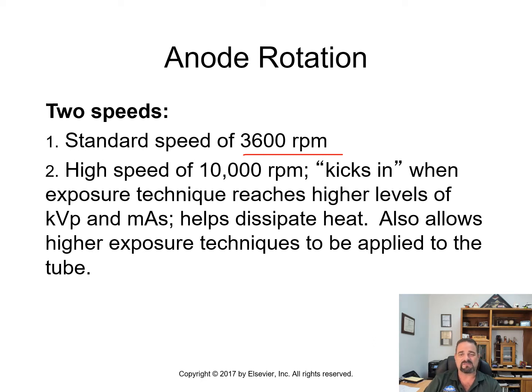You will hear this spin up when you first turn on your radiographic device, your imaging machine, in the morning. You're going to hear it spin up because it's beginning to warm up. This also allows for the higher exposure techniques to be applied to the tube.